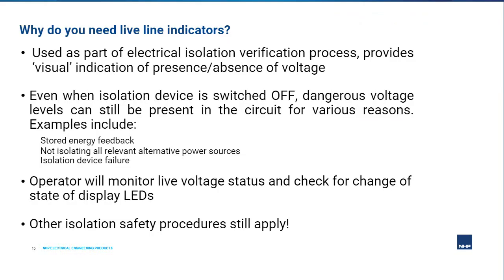So why do we actually need liveline indicators, and how does it improve personnel safety for operators servicing live boards? For this, it's worth reviewing the general electrical isolation process and the dangers this presents to the operator. Now, say you have a distribution board which is supplying multiple sub-circuits connected to loads. The service technician needs to perform maintenance, and hence they need to isolate the power source or sources to the loads in order to replace components as part of the maintenance function.